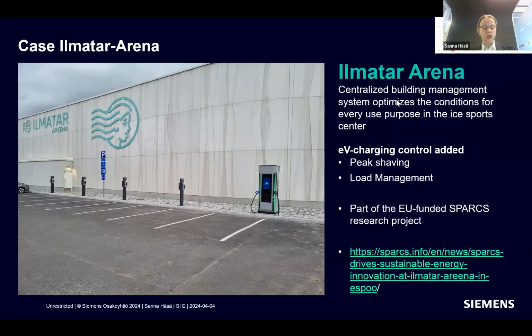So there is a lot of cooling equipment, and now they have installed their own PV plant there, and there's a lot of energy and electricity consumption inside the building. Then they wanted to install charging points there for the customers, and now these charging points are connected to the building management system in order to balance the power consumption of the building and the charging points, so that they don't exceed the grid connection level. So basically what's being done there is peak shaving - if you have very high power in general, you can take the peak off, so you don't consume so much power, by load management, so that you can reduce the power if needed.